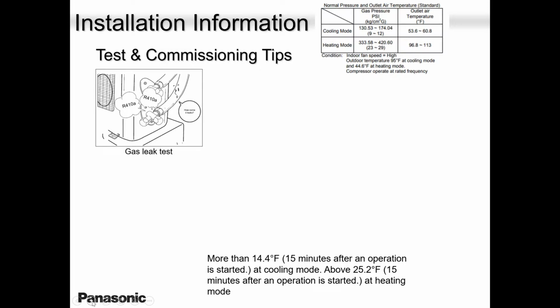Again, in heat mode, if you are low on refrigerant, you'll get a call of frost building up on the coil. You'll get a call of the unit going into defrost all the time. So please make sure you have enough refrigerant. You don't have too much. You don't have too little. You just have it on the dot.